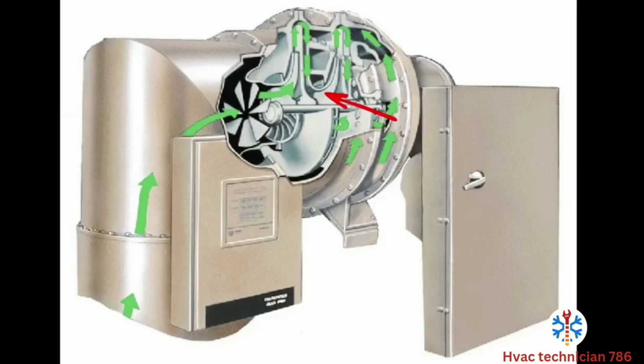Then this second stage, depending on if we have a CVHE or CVHF, will be a fixed or variable guide vane. So the difference between a CVHE and F is how many stages we have in the compressor. What is depicted here is a two-stage compressor, meaning that we have two impellers. You can see one, here's the second one back here, and then it's going to go straight to the condenser. A three-stage CVHE or G, you would have three impellers here. So in a CVHF with two impellers, it's two-stage.